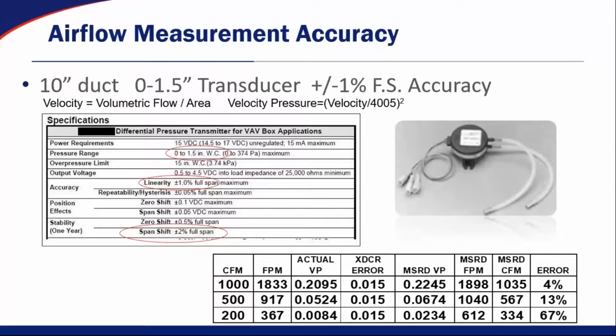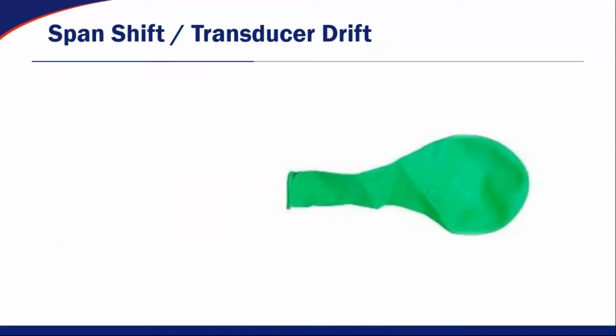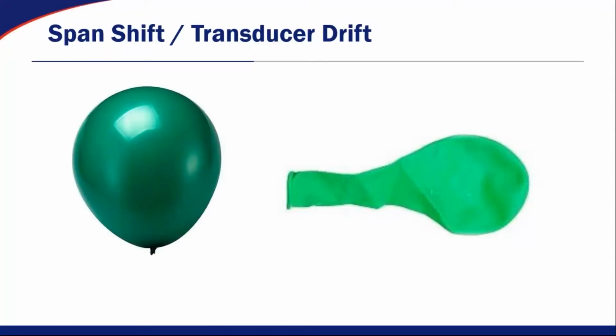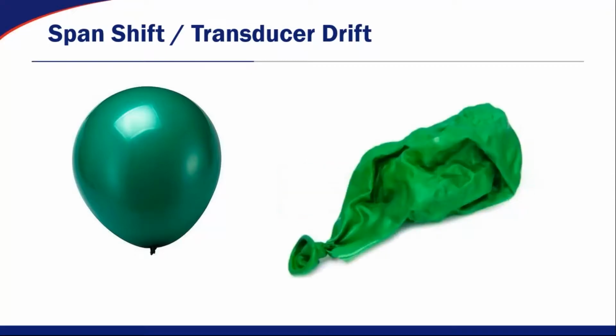Now, in addition to that, that is with a brand new, fully calibrated pressure transducer. One thing that's never really talked about on the bottom of that specification chart is a thing called span shift. The way I like to talk about span shift in a pressure transducer is if you think about a balloon. When you take a brand new balloon and you inflate it the first time, it's not very elastic. So it takes more pressure, it takes more effort to blow it up the first time. Well, after you let the air out of that balloon, every time you inflate it and deflate it, it's going to stretch more and more.